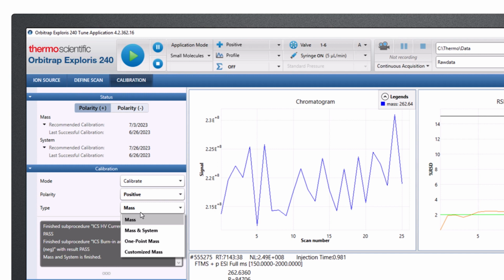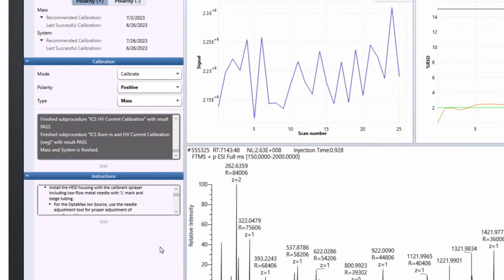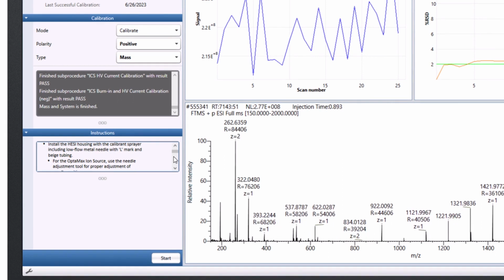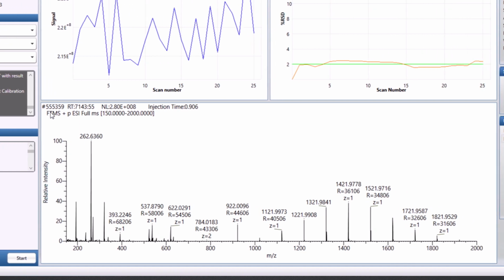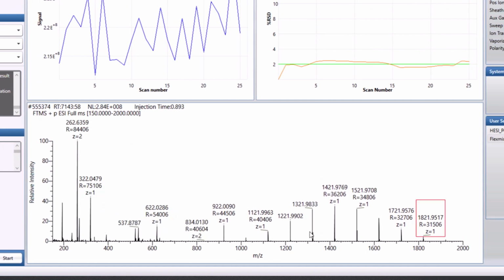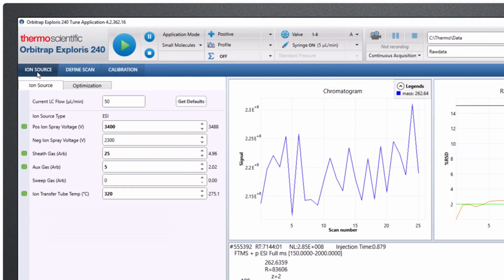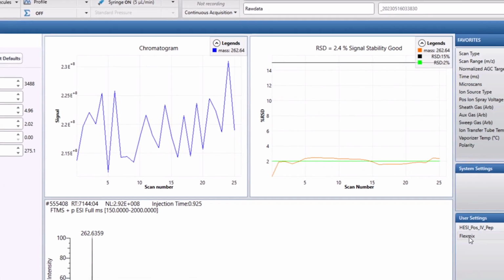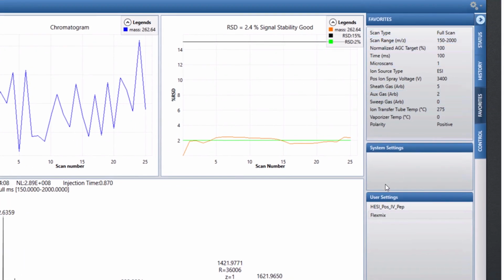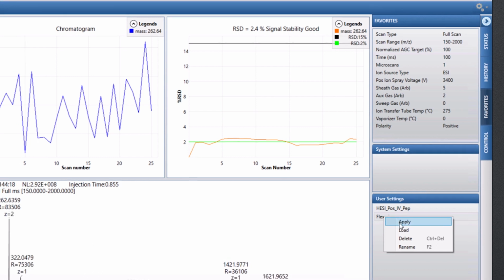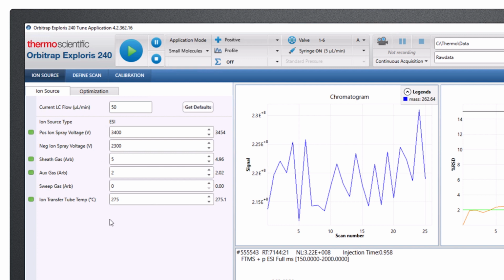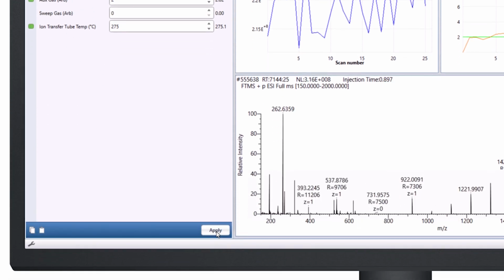So I can do mass or mass and system calibration, but I'm going to go ahead and show how to do a simple mass calibration, since this is the one that you'll be doing more routinely. And I have a nice set of instructions to the left to help me through. But basically, before you begin your calibration, what you're going to do is look at the nice display of ions collecting. You can go ahead and set your settings. Now, for my ion source settings, I have preset settings stored. So I have this flex mix tab selected, or settings saved, so I can go ahead and click apply, and it'll quickly upload the settings that you would use for calibration.